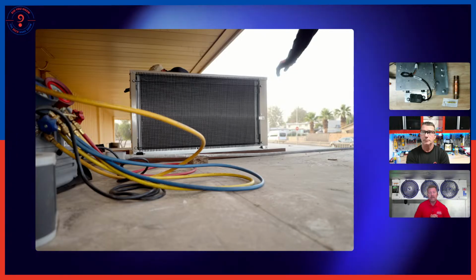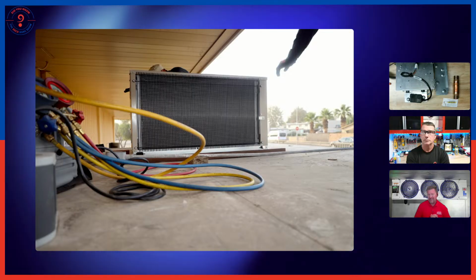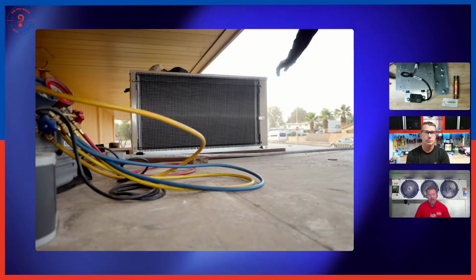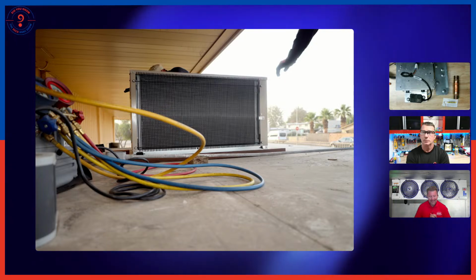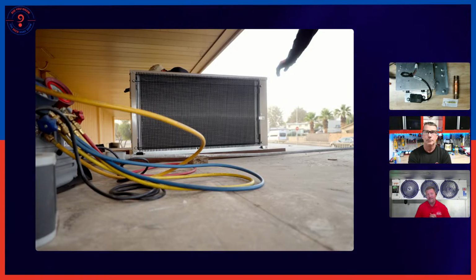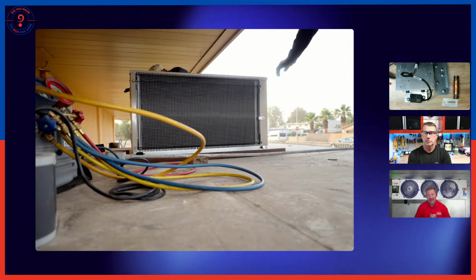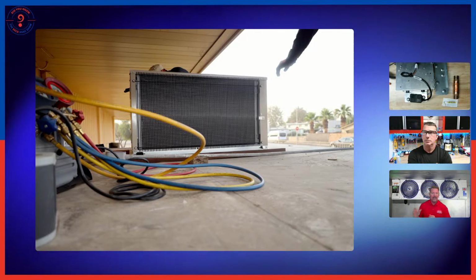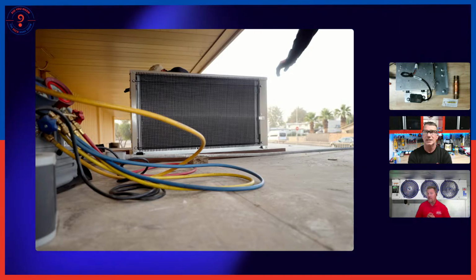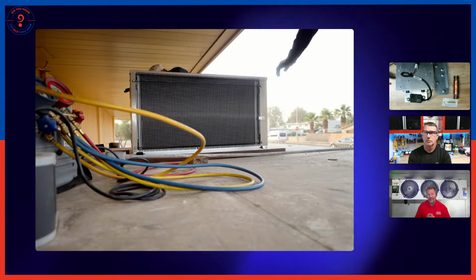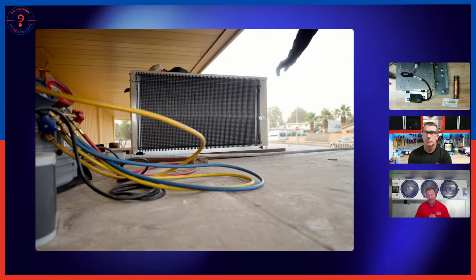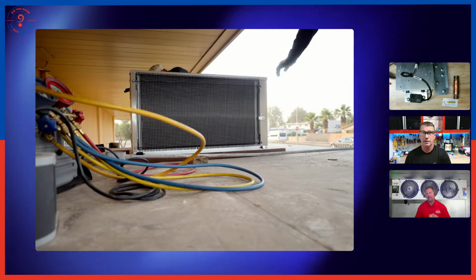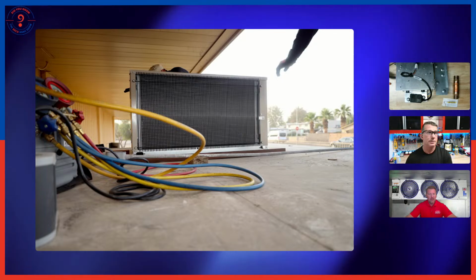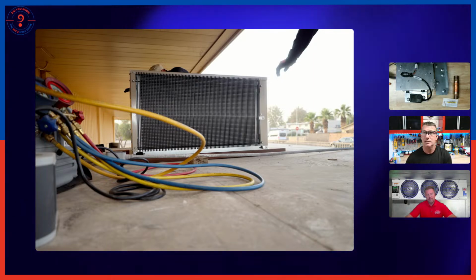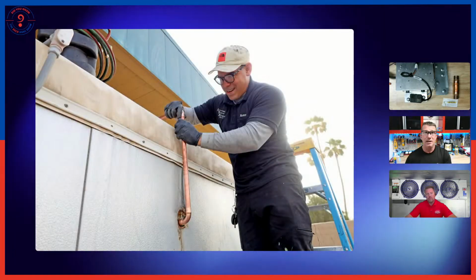A2L condensing units. Yeah. And the main difference you're going to see is on our receiver tank. Don Fort touched on this with you also, but we do have a traditional fusible plug on the receiver tank. The difference on these is we have a threaded addition that will allow us to put a piece of copper or some sort of tubing off of it to route the partially flammable gas away if this was an indoor installation. Yeah, which is very common. We see a lot of these inside of, especially restaurants, where it's indoors and it's just releasing its heat into the space. And so it gives the opportunity to plumb that outside. Yeah. Otherwise, it looks like a pretty common installation.